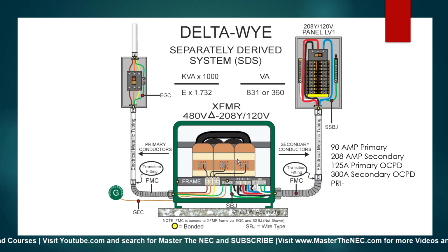So if this is 300 amps, remember if we were back in our part 1 series, that in order to calculate the secondary current, it was 75,000 divided by 360, which is 208 amperes. Okay, so it can only put out 208 amperes. But the secondary protection could go up to 125%. But if this primary was limited to 125, then technically we wouldn't need any secondary protection here. But for all intents and purposes, we don't worry too much about the top one because usually this is going to be your configuration right here. Okay, just know that if you didn't have a panel board here on the secondary and you were feeding something, then you would not necessarily need secondary protection. Okay, unless your secondary conductor rules stated that you did. Okay, all right, so let's get back to what we're dealing with.